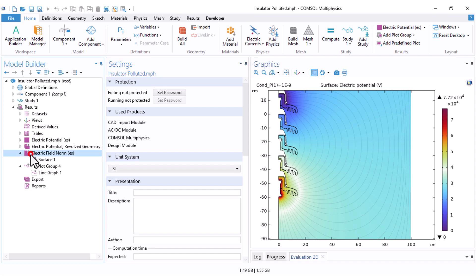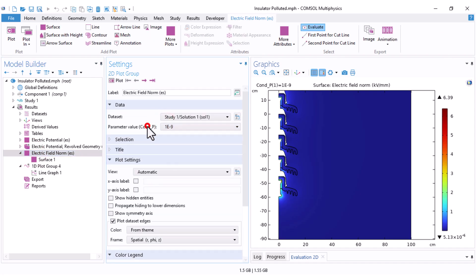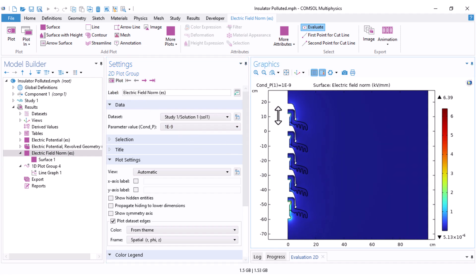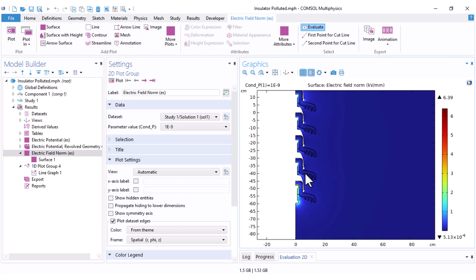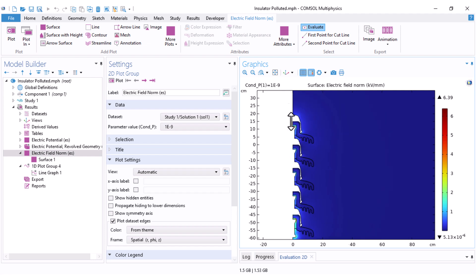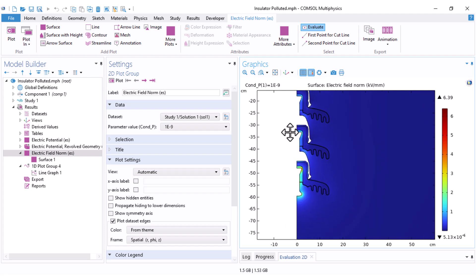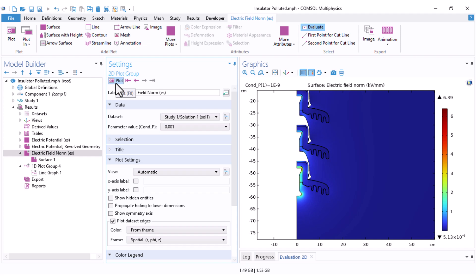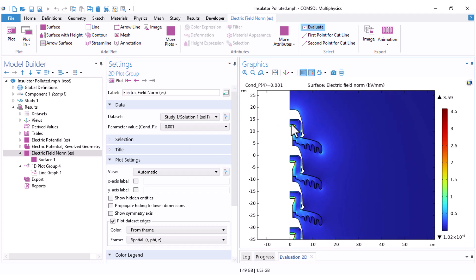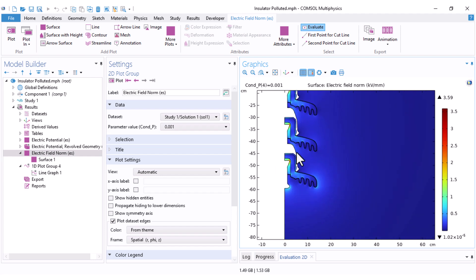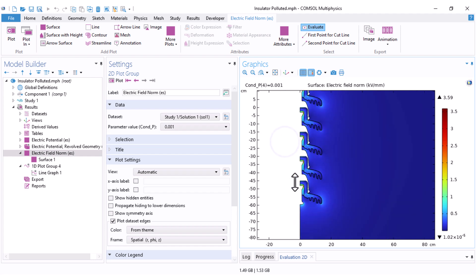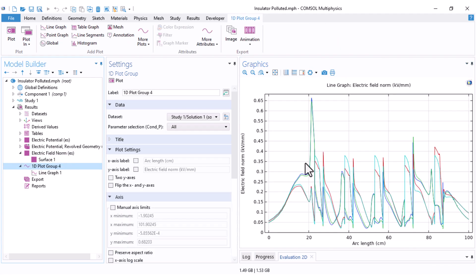Looking at the electric field distribution results, you can select your parameter value to compare cases. When pollution is light — similar to the clean condition discussed in the previous video — the electric field is very high at the two end sides of the insulator. But when the pollution gets heavy, the electric field distribution becomes more uniform. Clicking Plot shows that all units experience more or less the same electric field — this is the effect of a uniform heavy pollution layer over the insulator surface.